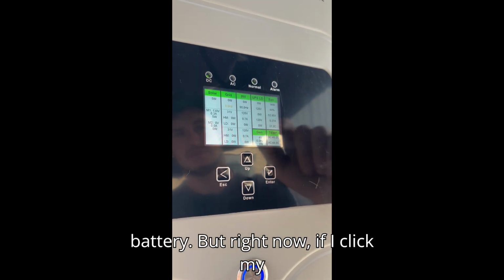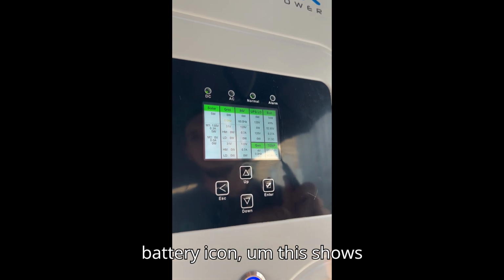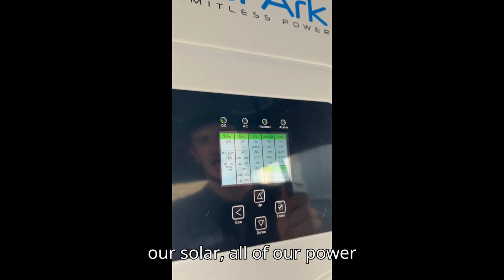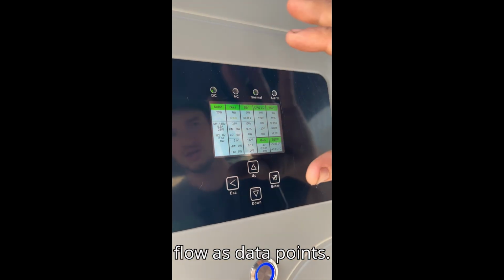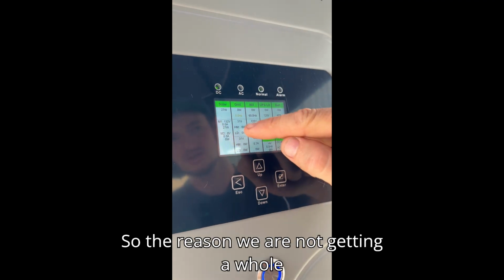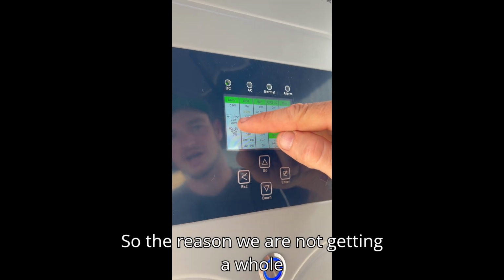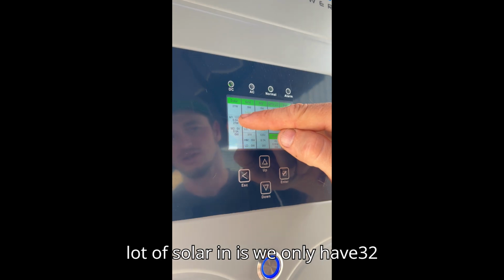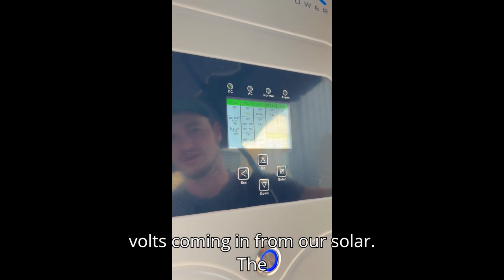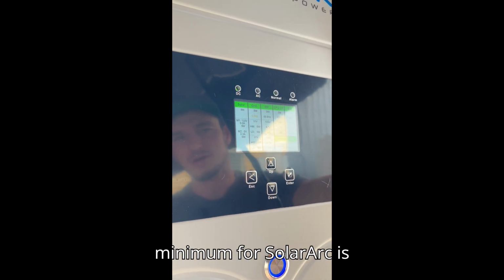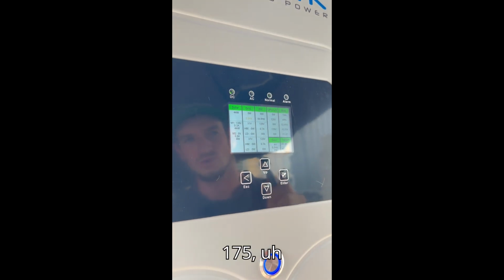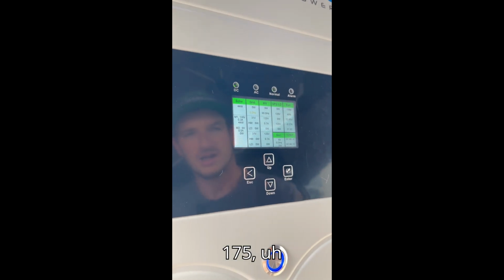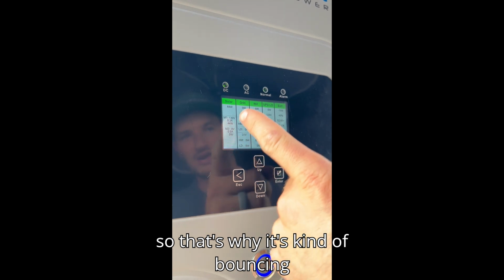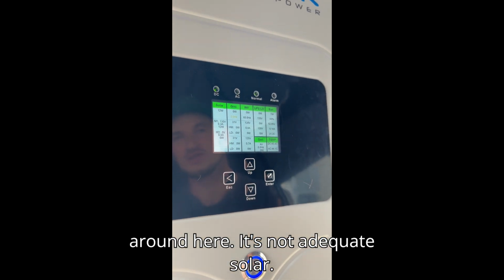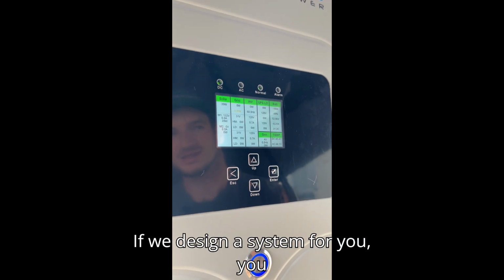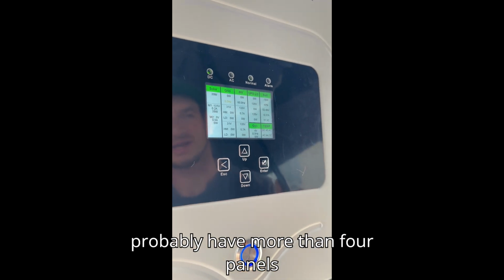Right now if I click our battery icon, this shows our solar, all of our power flow in as data points. The reason we're not getting a whole lot of solar in is we only have 132 volts coming in from our solar. The minimum for Sol-Ark is 175, so that's why it's kind of bouncing around here. It's not adequate solar. If we designed a system for you, you probably have more than 4 panels installed.